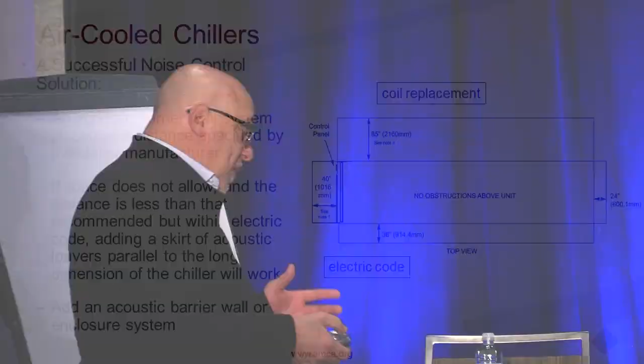So when we look at air-cooled chillers, the first thing we want to do is look at the installation instructions and placement instructions by the manufacturer. So this is really nice. It tells you, hey, we would like you to really have 55 inches here for coil replacement. We got electric code here, maybe the 40-inch, because we got a control panel here. You can get by with 36-inch here and 24-inch here. So if the noise control solution, like a barrier wall, can fit in those spaces, that's what we would want to do, because that's what the manufacturer is telling us.